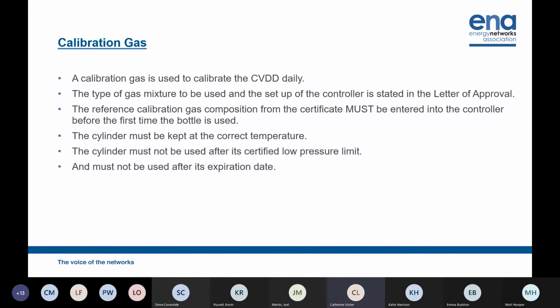No worries. Oh, Steve's got his hand up. Yeah, sorry to go back. You said towards the beginning about this shrinkage, this 37 figure, if your plant is not operated for a year. What did you mean by that? So if you say that you commissioned today and you haven't got a year's worth of records to go back to for your lowest CV in the last year, then if you had a loss of record on site, it will immediately drop to using a CV of 37. That's only in the case of a loss of record. A loss of record from SCADA?